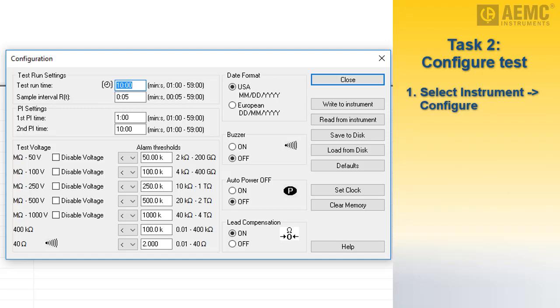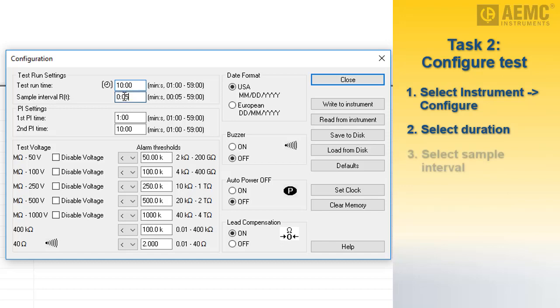We'll start by selecting the test duration. This can be from 1 minute up to 59 minutes. For our demonstration, we will specify 10 minutes. Next, select the sample interval. This determines how often during the test the instrument will make a measurement. We will leave this at the default setting of 5 seconds.